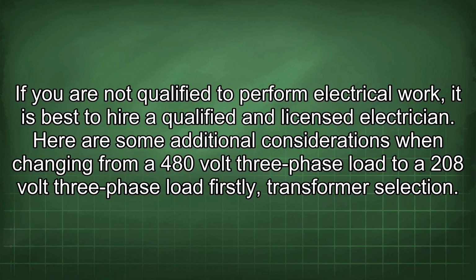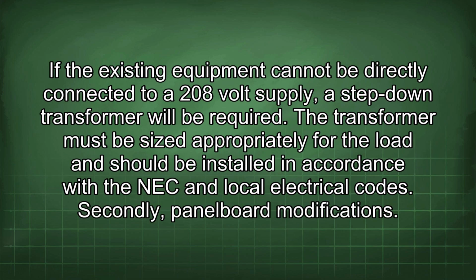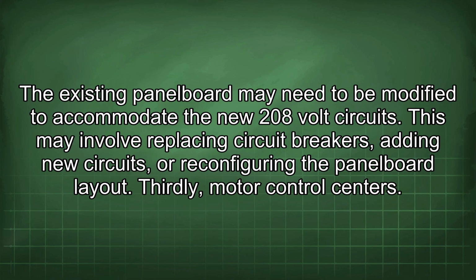Here are some additional considerations when changing from a 480-volt 3-phase load to a 208-volt 3-phase load. Firstly, transformer selection. If the existing equipment cannot be directly connected to a 208-volt supply, a step-down transformer will be required. The transformer must be sized appropriately for the load and should be installed in accordance with the NEC and local electrical codes. Secondly, panel board modifications. The existing panel board may need to be modified to accommodate the new 208-volt circuits. This may involve replacing circuit breakers, adding new circuits, or reconfiguring the panel board layout.